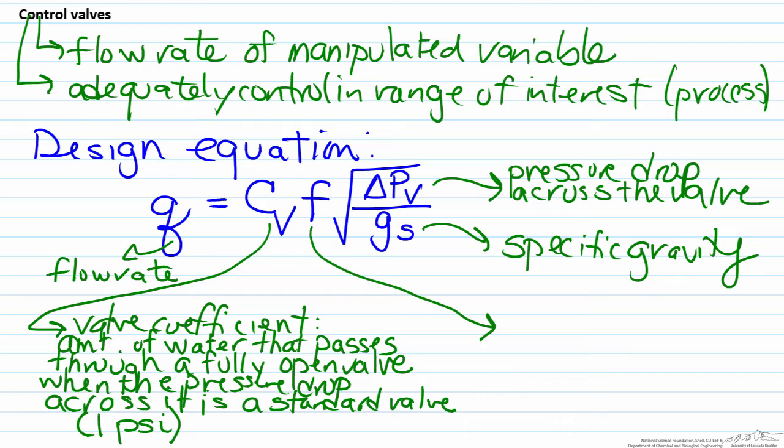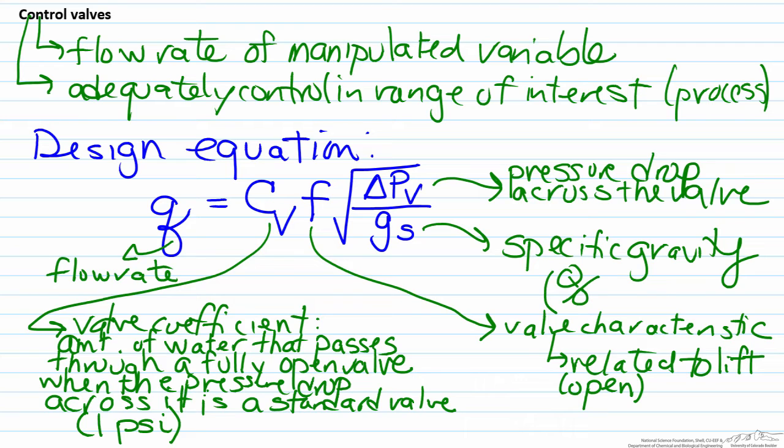The final value F is known as the valve characteristic, and the valve characteristic is related to the lift of the valve. In other words, how open it is. In a simple way the valve characteristic can be represented as the ratio of the actual flow rate going through divided by the maximum flow rate.